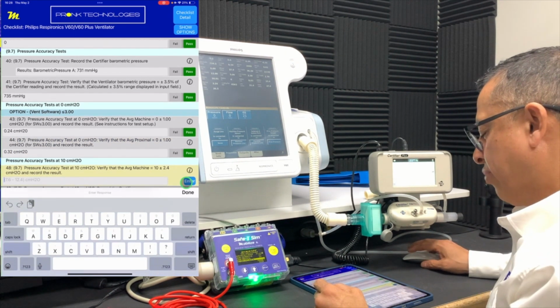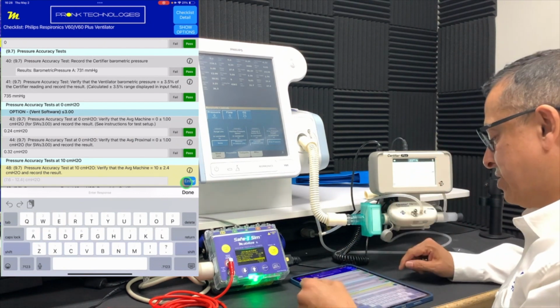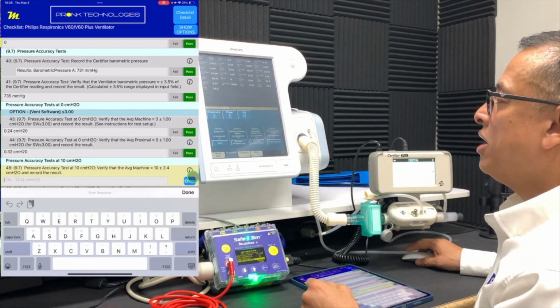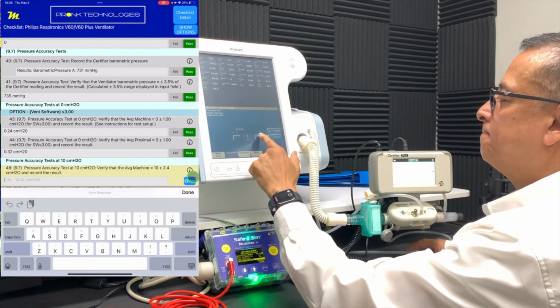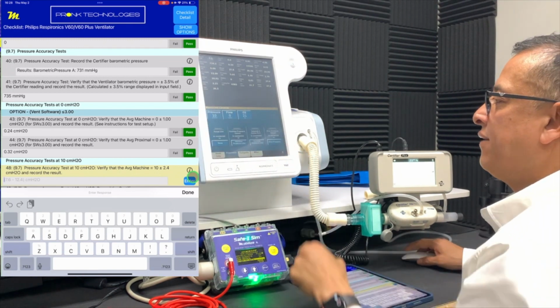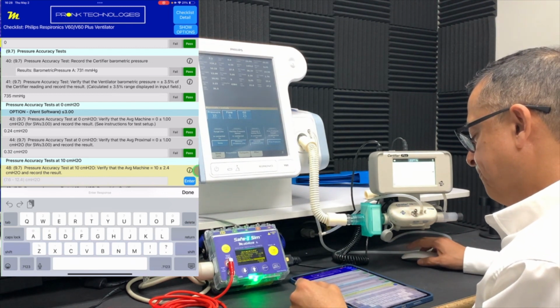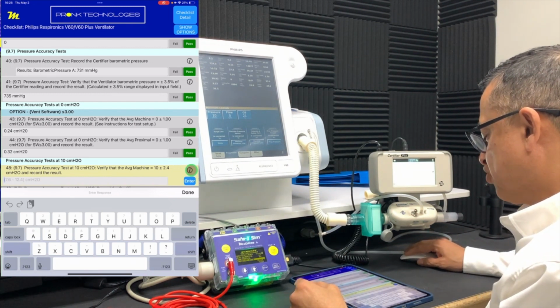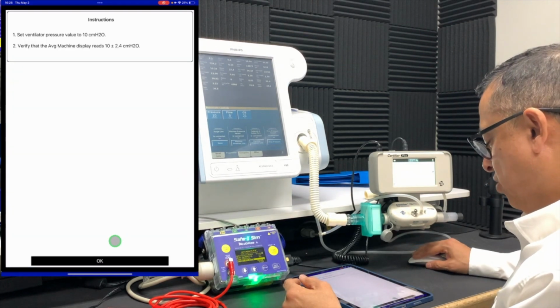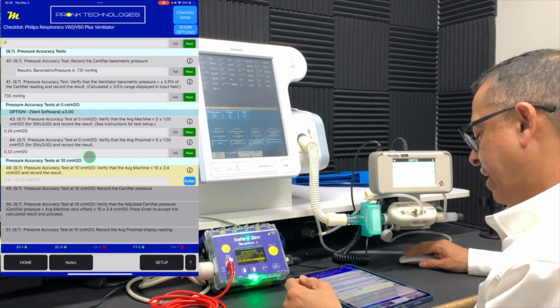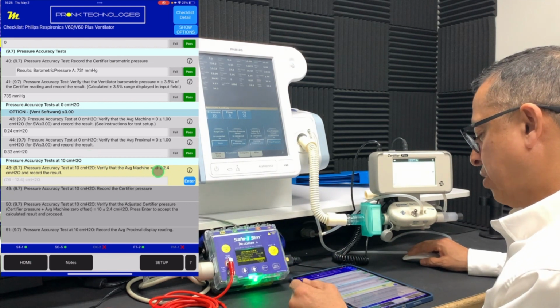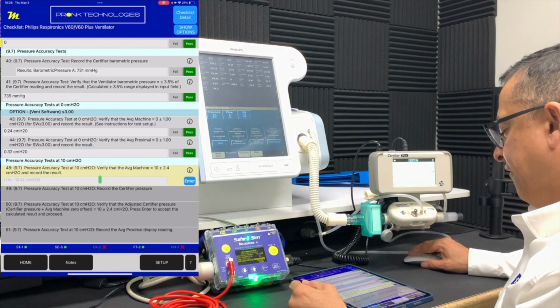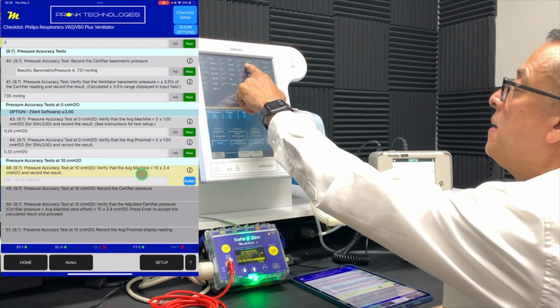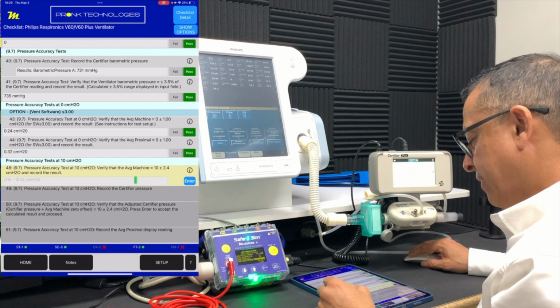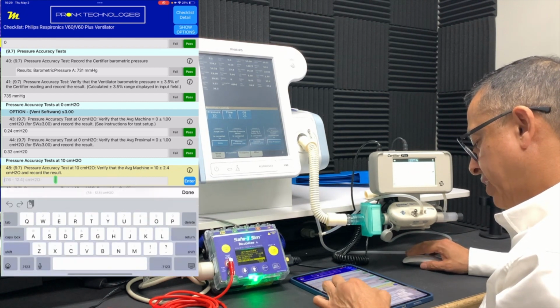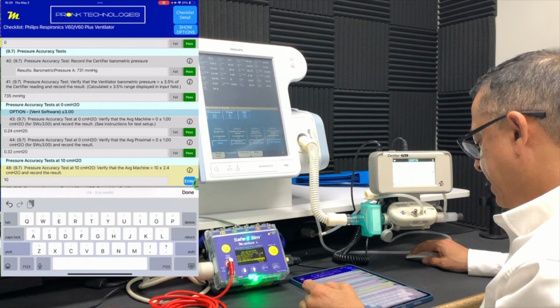And now we can go on to do the pressure accuracy test at 10 centimeters of water. Here, we're going to go ahead and set the pressure to 10. And again, if you're unsure of exactly how to perform those steps, you have the instruction here that can guide you right through that. So we have that value programmed. We need to make sure it's within this particular range, and we need to verify that the machine pressure is at 10, and it is exactly at 10. Again, our pass-fail ranges are here. I enter in my value of 10, and we finish that test.